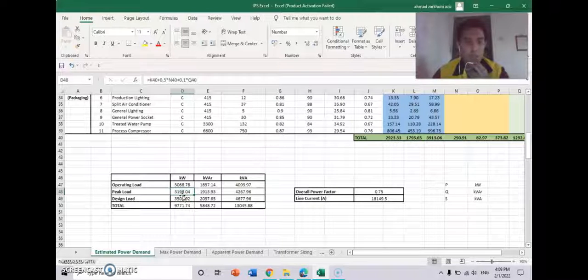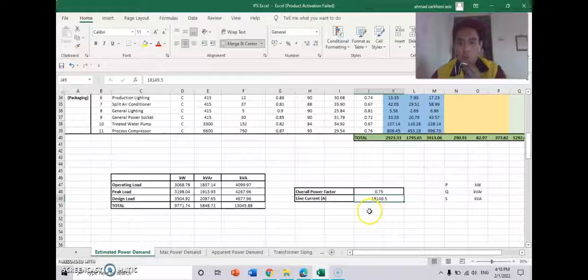For peak load we use this formula, and for design load we use this formula. And to get the overall power factor, first we need to add D40, which is the operating load, plus peak load plus design load, over the operating load in kVA plus peak load plus design load. So we will get 0.75. And this is the value for line current, which is 18149.5. So that is for the estimated power demand.